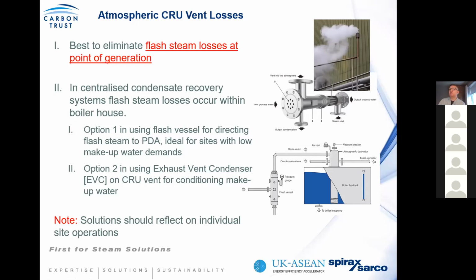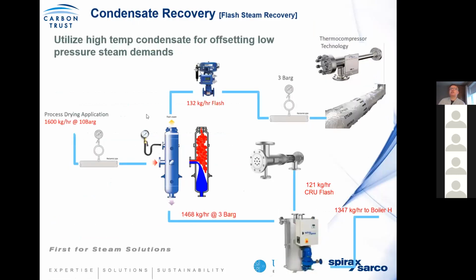Can you incorporate it in the boiler feed water? If not, you look at the process that's actually generating it to see, can you use it to preheat process makeup water? So for example, we give a case here of a process application that uses 1600 kg an hour of steam at 10 bar. What you do is you put in a flash vessel, and you depressurize the condensate. You could even create low pressure steam for end users, or you could use technology like a thermocompressor, where you use the flash steam and recompress it back up to a working temperature.